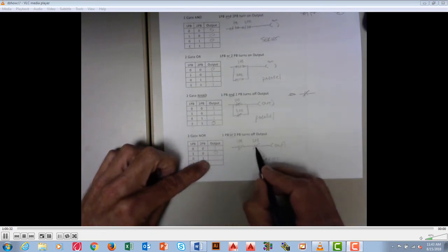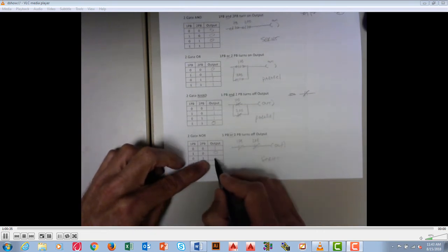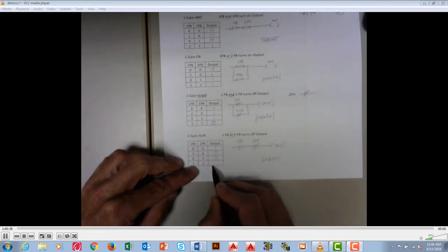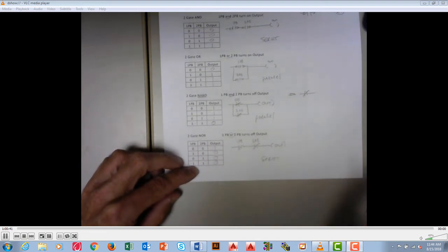Okay, put a 1 in there. And so if I put a 1 here, where 1 PB is, that's going to open. So as soon as that opens, this goes off. If I put a 1 here on this one, well, that's going to open, causing that to go open. And obviously, if I put a 1 here and a 1 there, it won't be true, and it would go off. So the NOR, the NOT logic, dictates that these are in series, whereas the OR with the open contacts is in parallel. And we'll do some more switching, looking at this a little bit later.